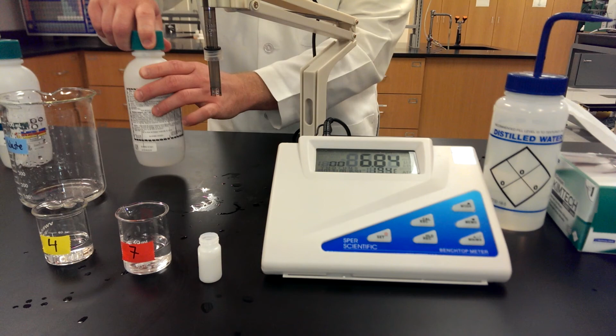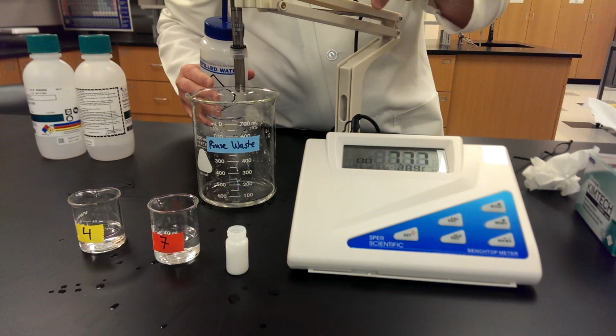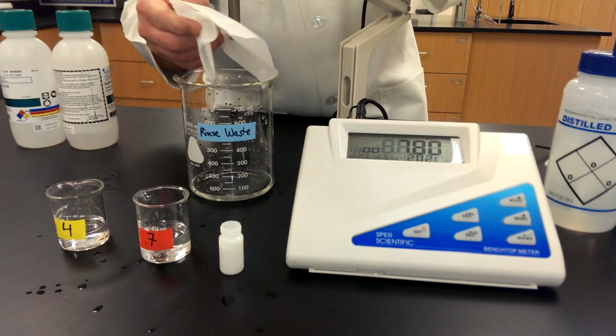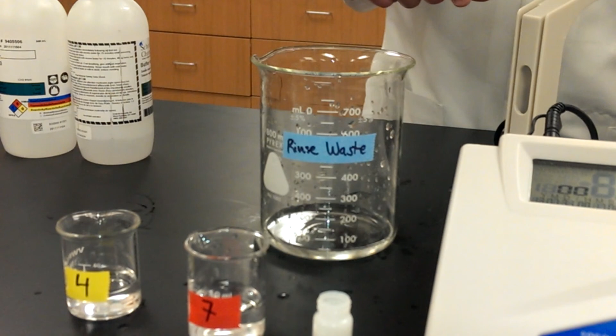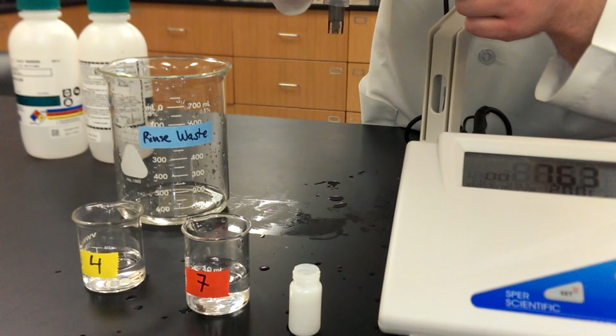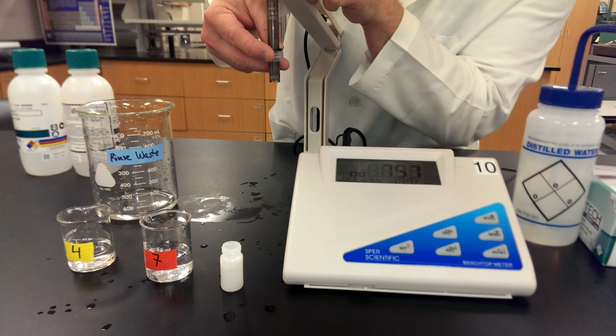I'm going to rinse the electrode. Now remember, this is what you do after your experiment. That way the next student that uses the benchtop meter after you gets a pH meter that's correct. And again, we're going to dab it dry with the Chem wipe. Alright, once you've done that, go ahead and slide this back down. Remember, I slid this up earlier. So you should have about an inch or an inch and a half there of electrode below this screw cap here. And remember, never take this off.